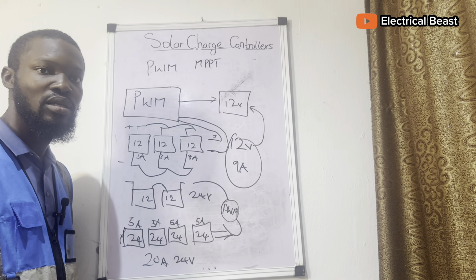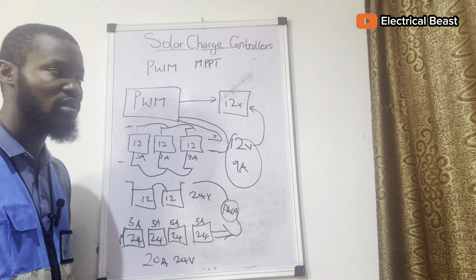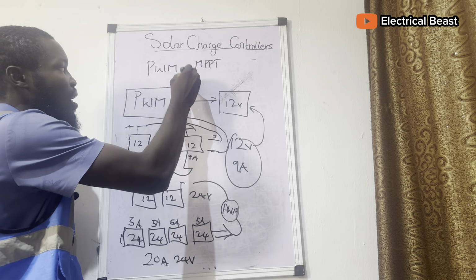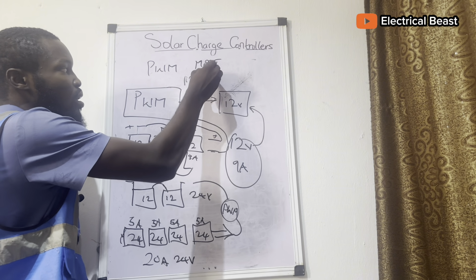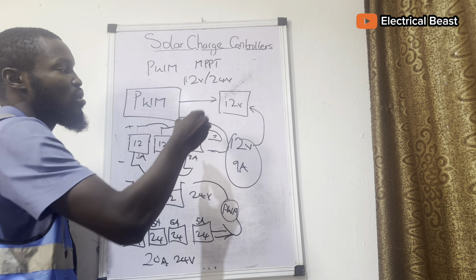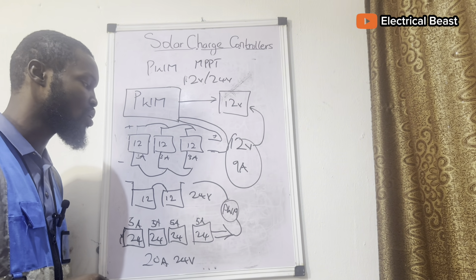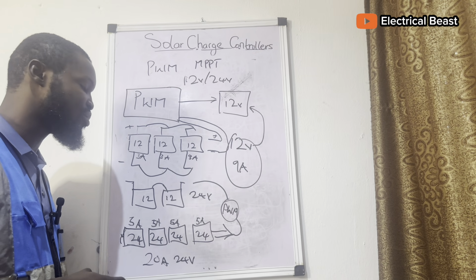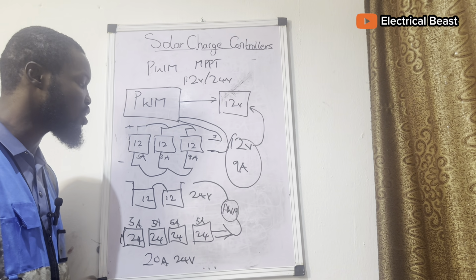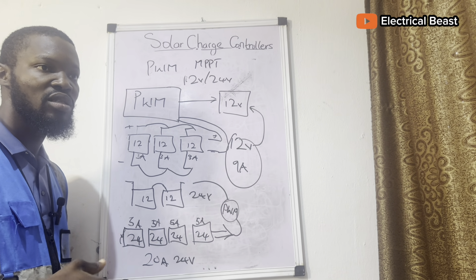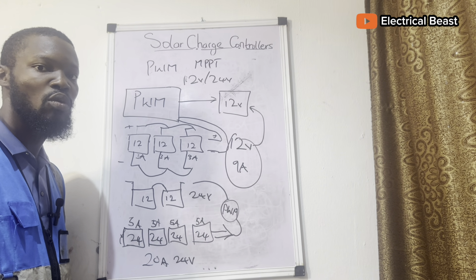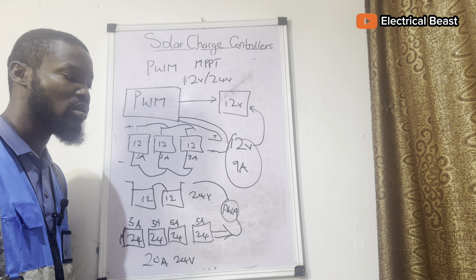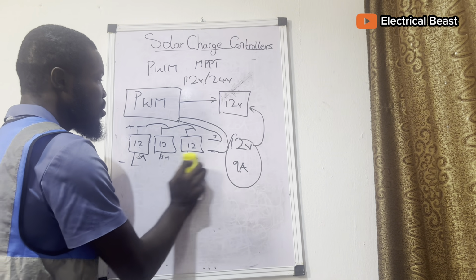Each charge controller has a current rating and also a voltage rating. There are some charge controllers that accept both 12 volts and 24 volts. It is always written on the nameplate of the solar charge controller. So as much as possible, try to avoid series connection, because series connection makes the voltage more than what is required, more than what is needed. So that is that for PWM controllers.